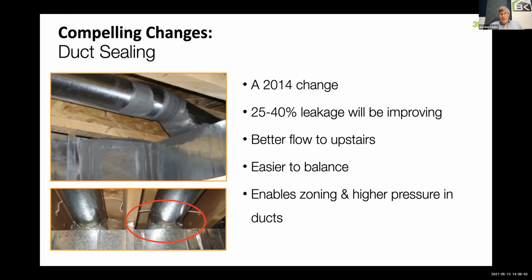We now have in our code that you have to seal at least the transverse joints. You don't have to seal all the joints. Of course, you should seal all the joints, but you don't have to. And that's the duct leakage used to be at 25 to 40%. You're going to see here in a second where it's gone down.